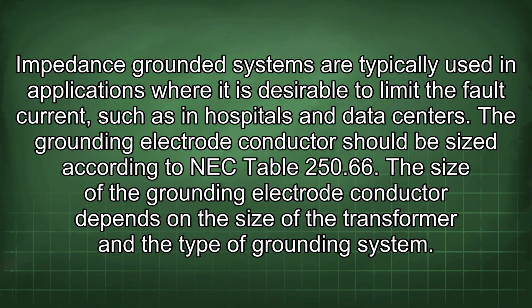Impedance grounded systems are typically used in applications where it is desirable to limit the fault current, such as in hospitals and data centers. The grounding electrode conductor should be sized according to NEC Table 250.66. The size of the grounding electrode conductor depends on the size of the transformer and the type of grounding system.